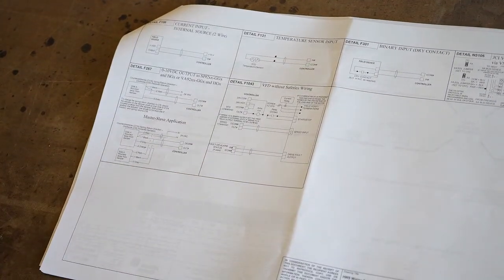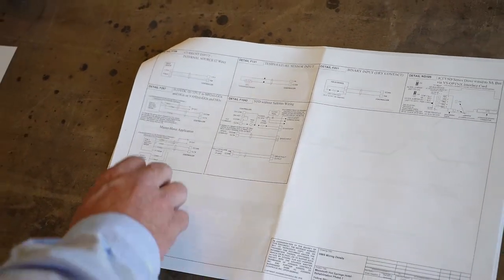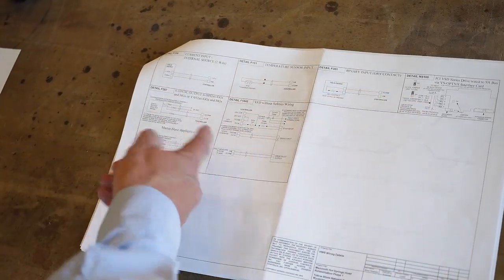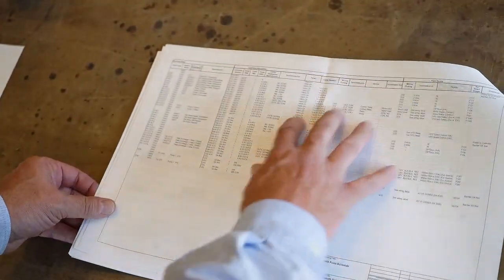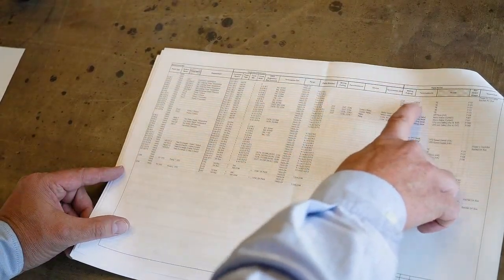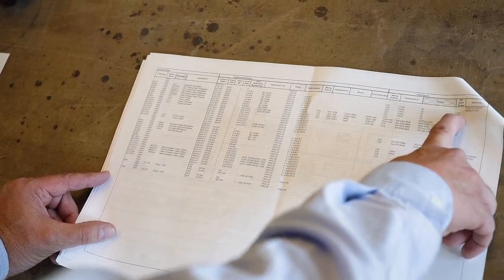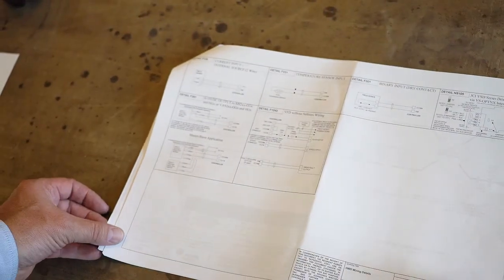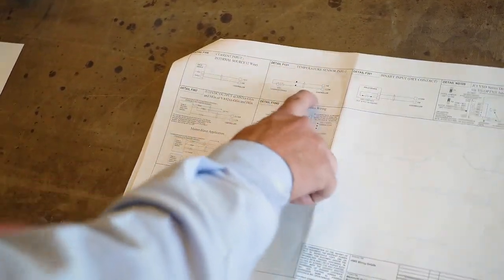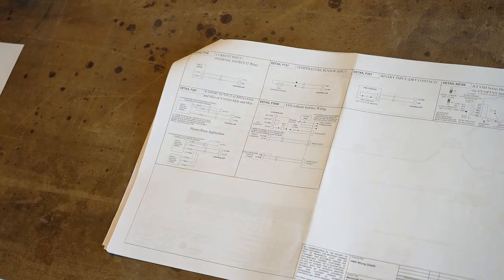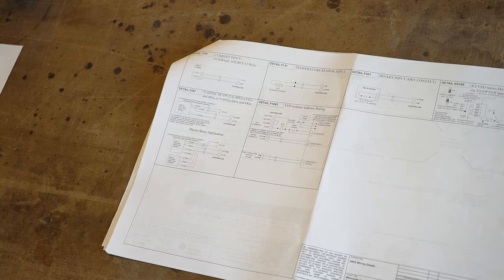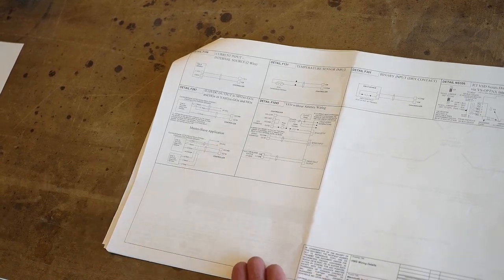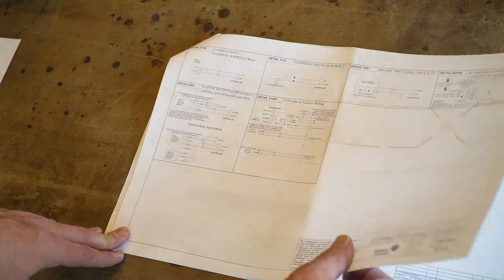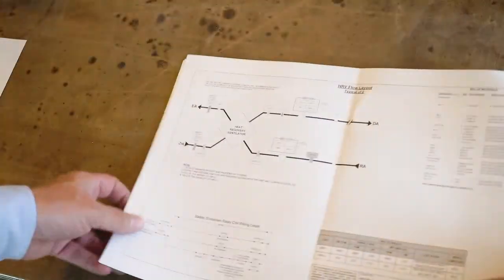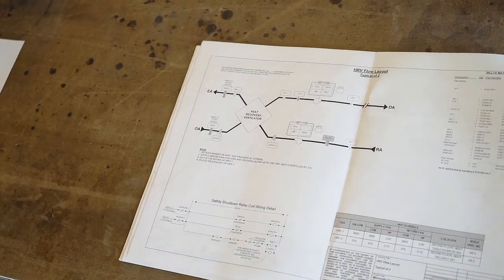The next sheet is our wiring diagram. I'll have to flip back and forth here a little bit. This tells you how the connections are made for each sensor and how they're wired. So for instance, on an outside air temperature sensor, we'll follow that all the way across here, and it tells you reference detail sheet F131. So then you come over here and you find your detail F131 and it gives you the wiring diagram and how they should be terminated. Okay? So that's standard for all those items on that point schedule. They reference the information on this wiring detail sheet. And some of that can be handy because you're gonna have Darwin on the phone explaining where to go, where to find. Oh, no, you didn't have to watch Darwin's video. Yeah. That's right. That's right.